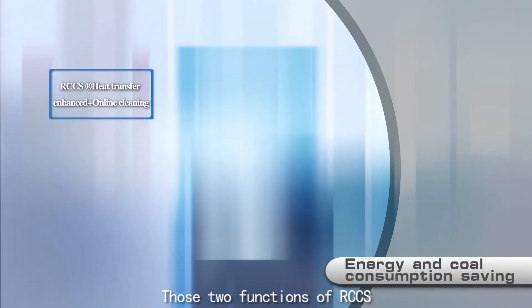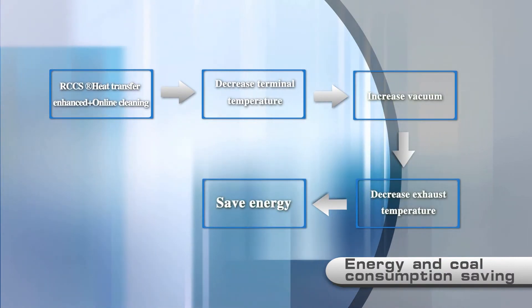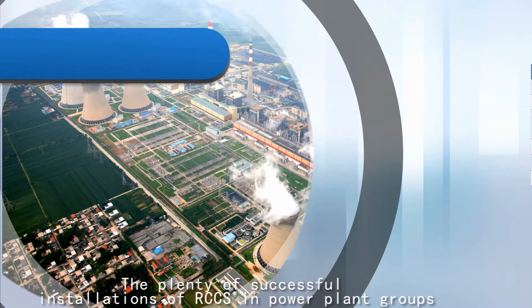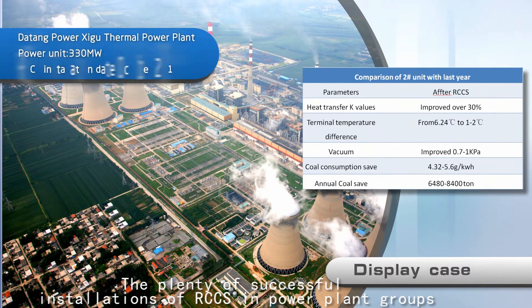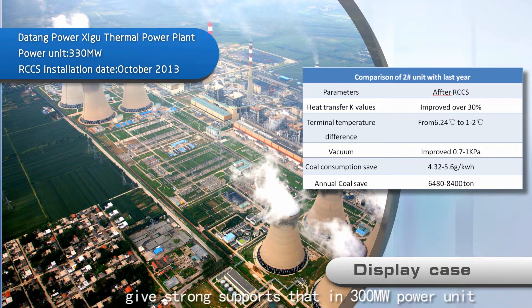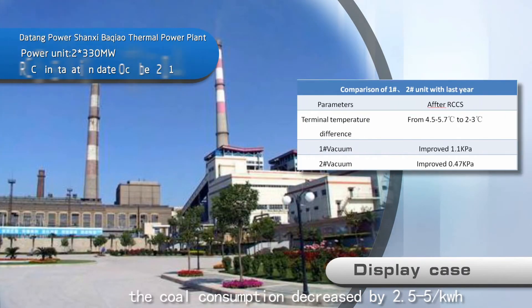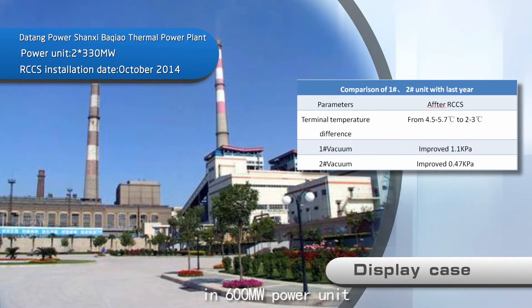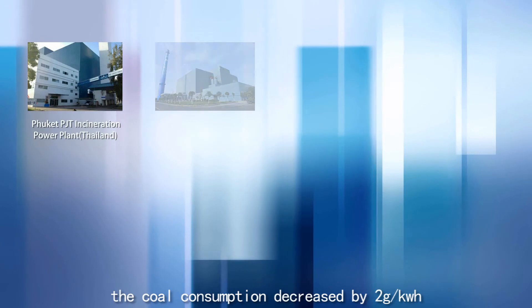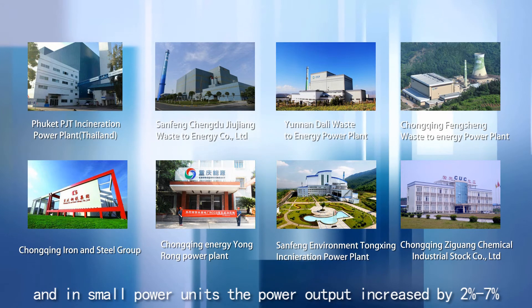These two functions of RCCS make energy and coal consumption savings a reality. The many successful installations in power plant groups, steel and cement industries, and petrochemical fields demonstrate that in a 300 megawatt power unit, coal consumption decreased by 2.5 to 5 grams per kilowatt hour; in a 600 megawatt power unit, coal consumption decreased by 2 grams per kilowatt hour; and in small power units, power output increased by 2 to 7%.